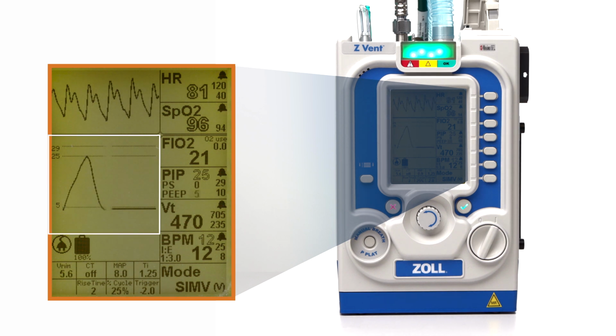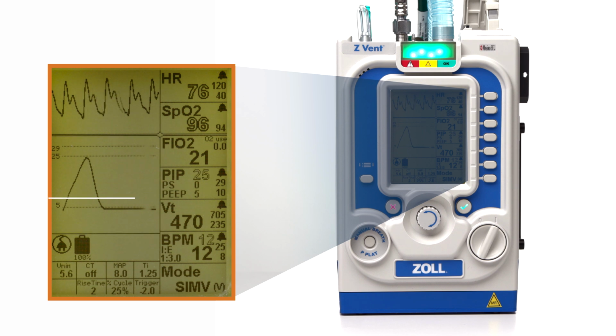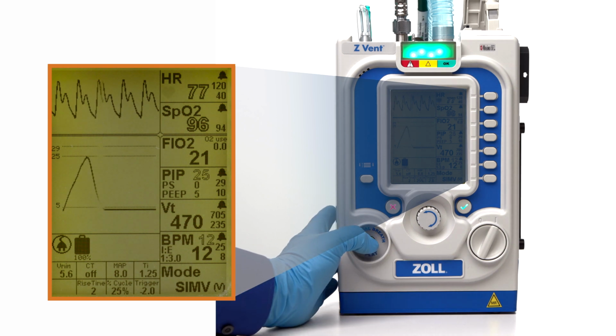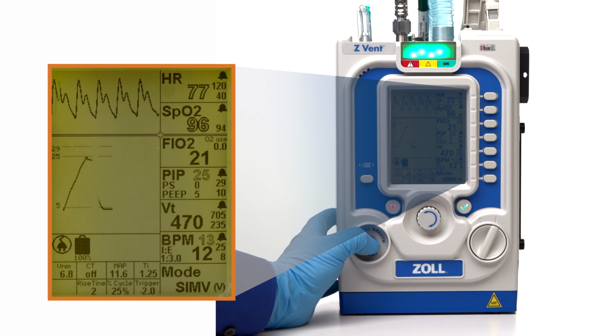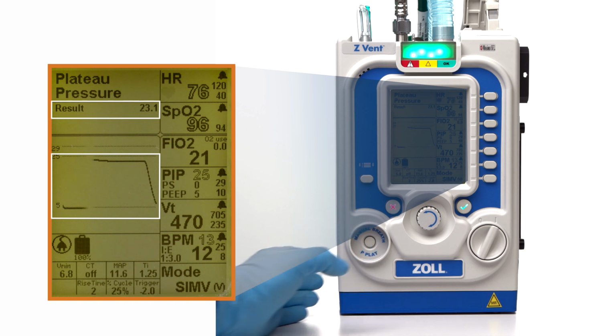The pressure time waveform is displayed directly to the left of the PIP parameter window. This waveform displays, in real time, the patient's PEEP level, the actual PIP, and the high pressure limit. The waveform plots airway pressure against time and is automatically scaled based on the breathing rate, PIP target, and high pressure limit alarm settings. When operating in volume-targeted breathing mode, pressing the manual breath/plateau pressure button changes the displayed waveform to a plateau pressure waveform measurement and displays a numerical result.